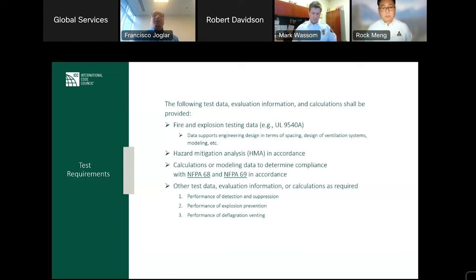The UL 9540A test data is necessary. It includes what they observe in the test, but also measurements of the gas concentrations that is used to support the modeling and the design of systems. I mentioned that. It's heavily referenced in the hazard mitigation analysis. It's used to support the design, right, of the deflagration venting and the ventilation, the explosion prevention. And basically it's a key input to our performance-based mitigation design. So it highlights what the operator really needs to collect when they are buying and installing these batteries. I already mentioned all the design information that is needed, plus all the performance associated with the batteries. Next slide, please.